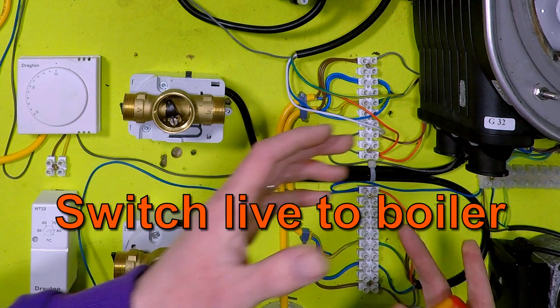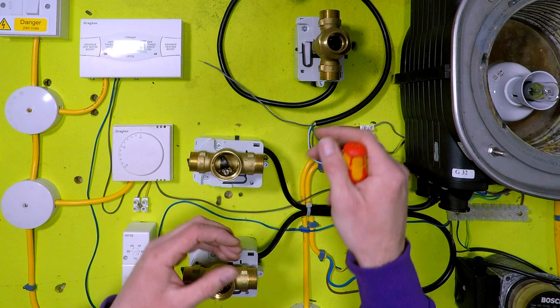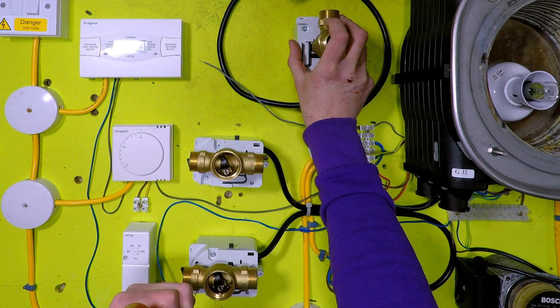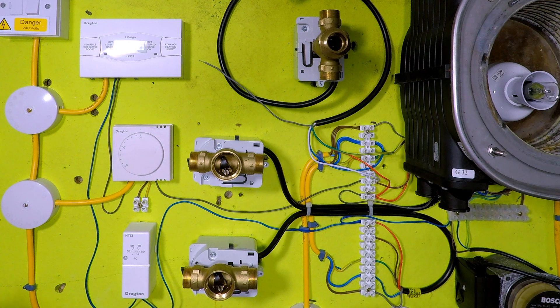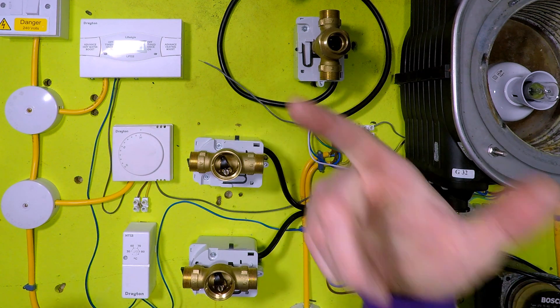And then the cylinder stat is saying I want to be heated and where does it send that power out? Down this wire here and it goes into the orange, so it runs the boiler again. All on a heating and water demand, all the three port does when everything's calling for heat is go to mid position. It doesn't do any demanding, doesn't send power anywhere. It just moves to mid position. That's it. So we're going to create a heating only demand.